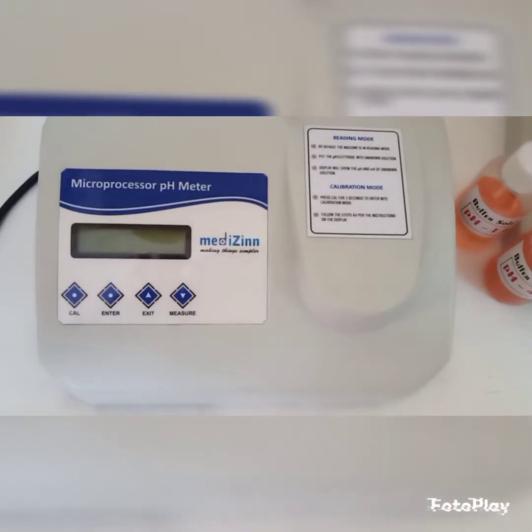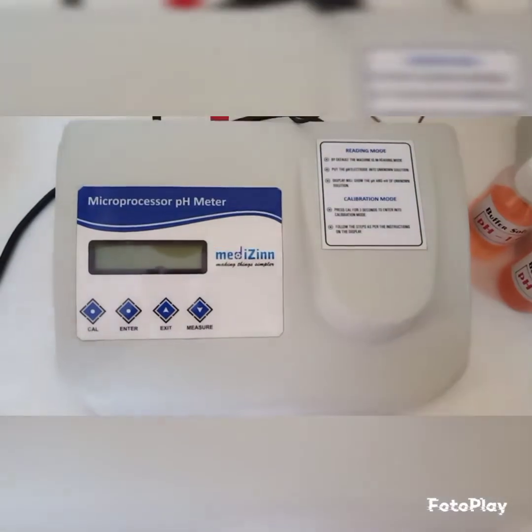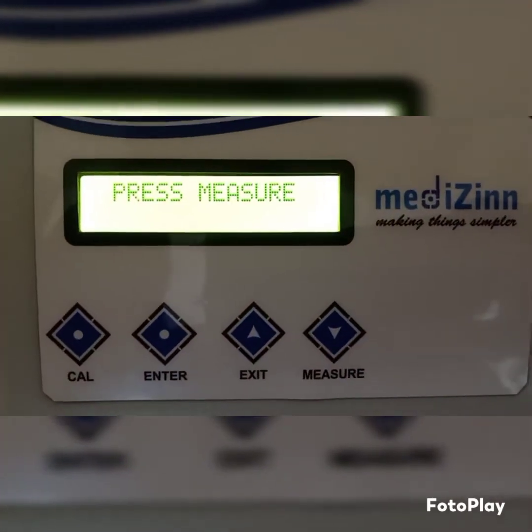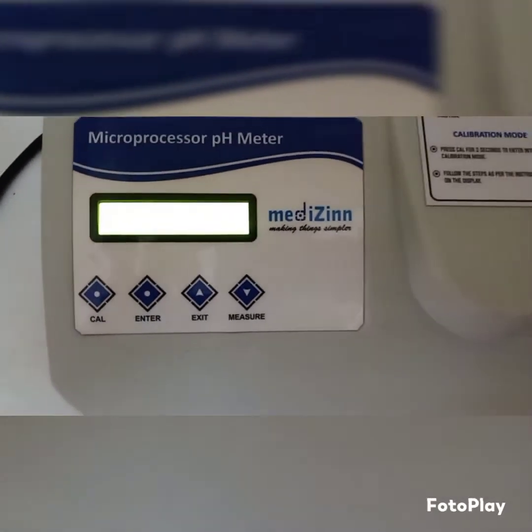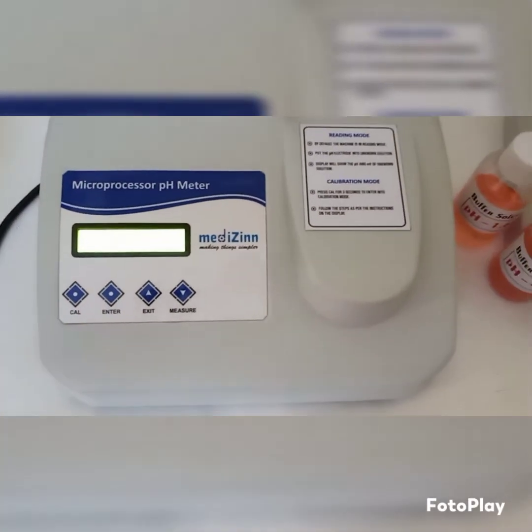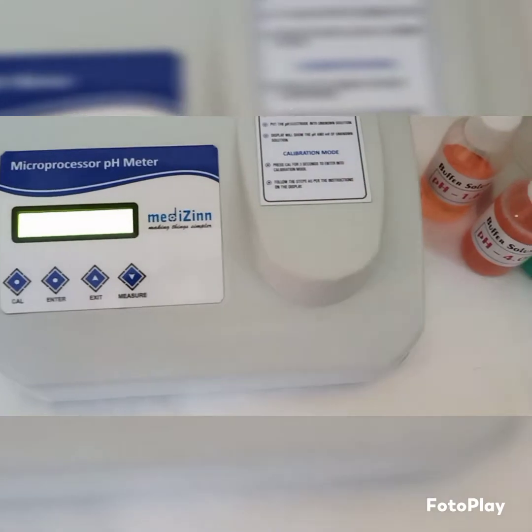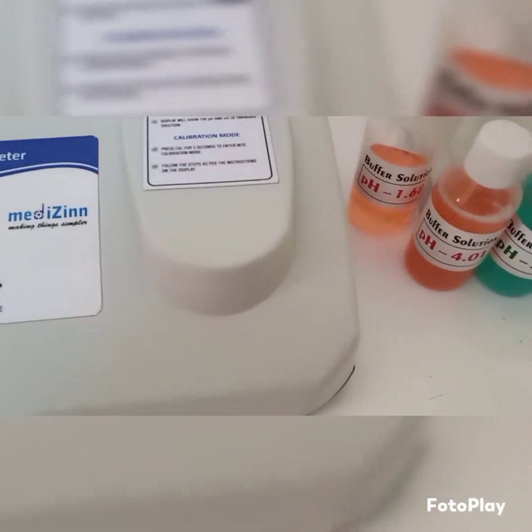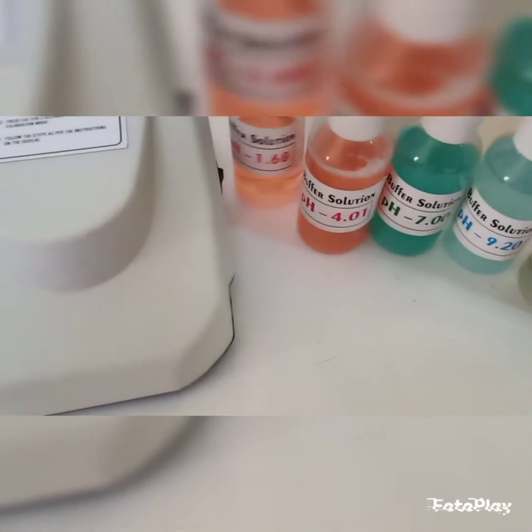This is an industrial microprocessor based pH meter, make mediZinn, model MZ113 NR. It's a 5-point calibration with buffer 1.68, 4, 7, 9.20 and 12.45.